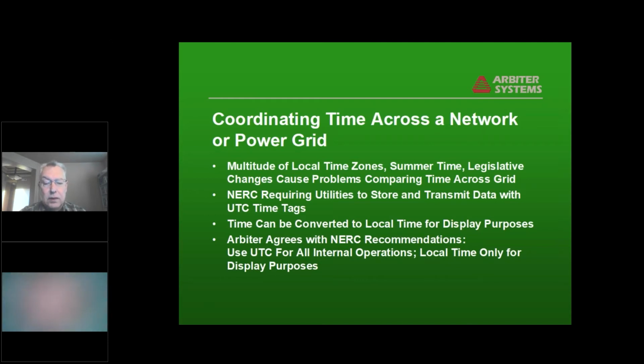And we endorse the NERC recommendation to use UTC for all internal data transmission. That means that information can be exchanged between multiple utilities on a common time frame. But there's no problem with using local time for display purposes. And you can set your substation clocks to generate the UTC time tags and UTC IRIG signals for your IEDs and so forth, and then have a local time feed on, say, a serial RS-232 port that drives a display. They have that kind of capability, so it's certainly feasible to do that. And you can also apply the local time correction in an IED. The information in the IRIG time streams and PTP and other ways of getting the time out have those local offset numbers in them now.